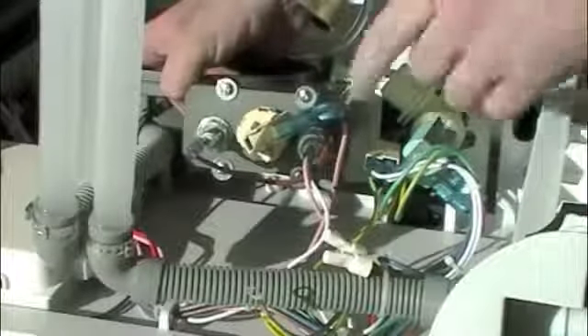So you're going to disconnect your wires here at the thermostat. You always want to do a resistance test on your thermostat. Obviously you should be able to do that. And you're also going to do a resistance test between this terminal and this terminal here on the ends of that element that I just showed you.